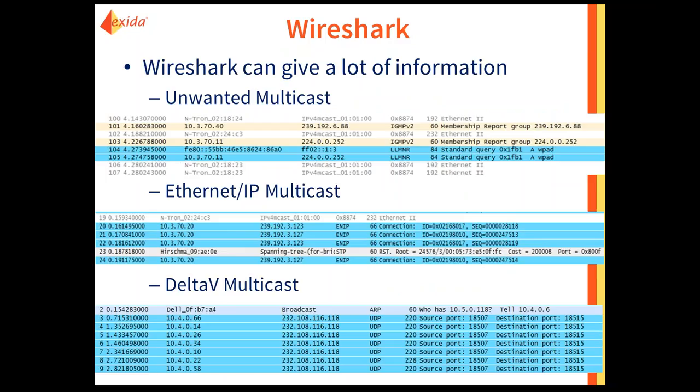Integrated sniffing within a firewall is available on some firewalls — when you put the firewall in place you'll see the traffic passing through it, so you don't have to create a separate Wireshark mirror. Wireshark is an extremely valuable tool. In some examples: there's unwanted multicast traffic, IPv6, logical link layer traffic, and Internet Group Management Protocol — traffic I don't want reaching my end devices. In the middle capture there's Ethernet IP real process control traffic, and on the bottom there's Delta V traffic with multicast destination addresses.